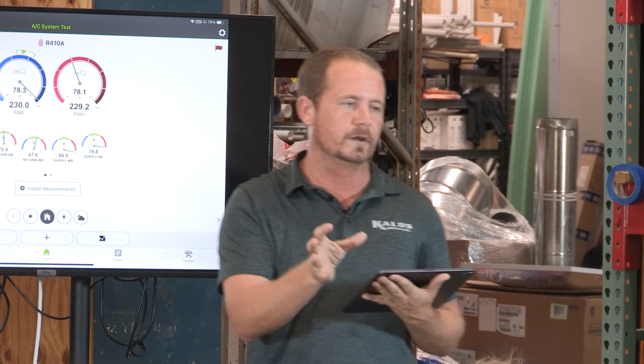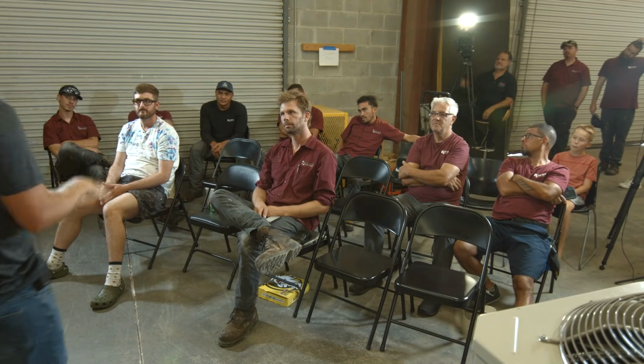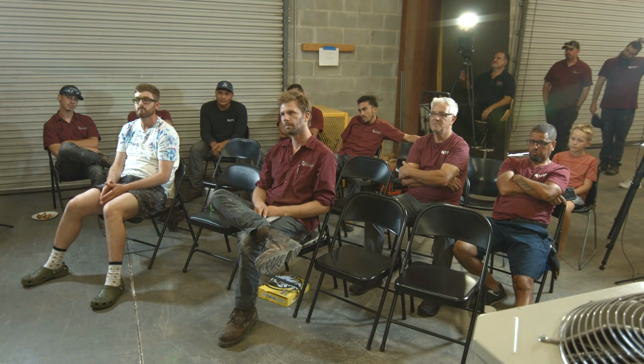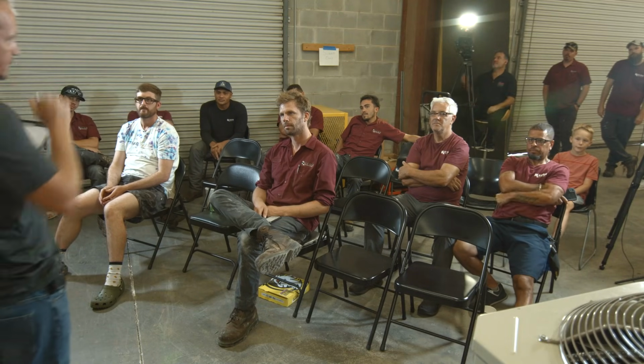All right, so there is this fine line. Can you overload a compressor by having the suction gas be too heavy? No. Just on the other side. Can a compressor actually do so much work because the suction pressure is so high that it overloads? Heck yes. The answer is yes.